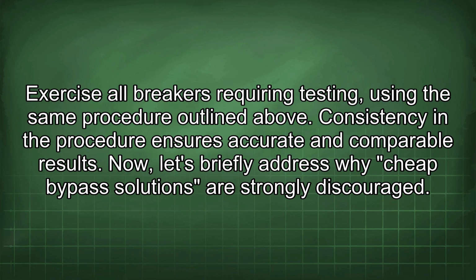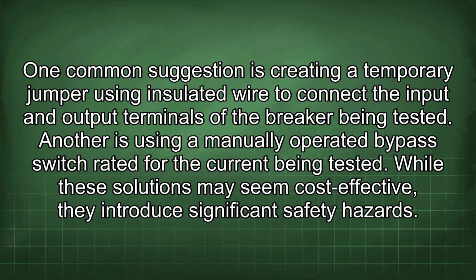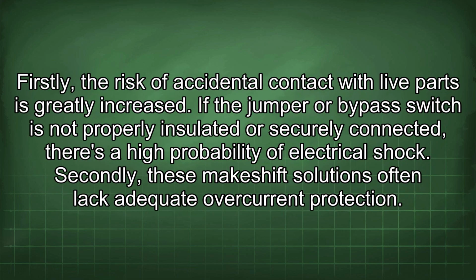Now, let's briefly address why cheap bypass solutions are strongly discouraged. One common suggestion is creating a temporary jumper using insulated wire to connect the input and output terminals of the breaker being tested. Another is using a manually operated bypass switch rated for the current being tested. While these solutions may seem cost-effective, they introduce significant safety hazards. Firstly, the risk of accidental contact with live parts is greatly increased. If the jumper or bypass switch is not properly insulated or securely connected, there's a high probability of electrical shock.